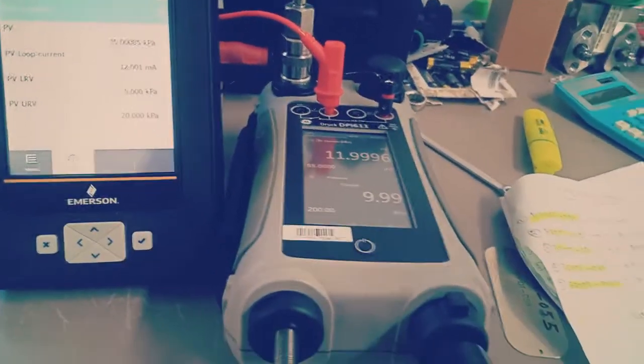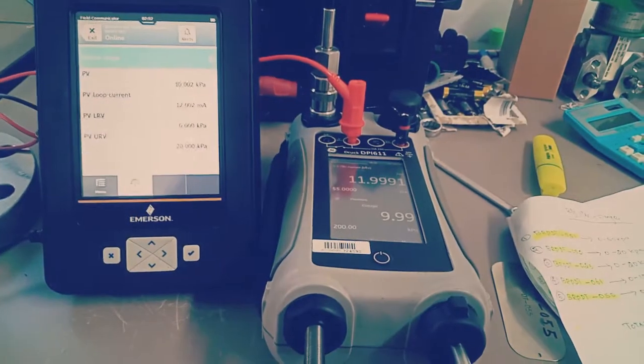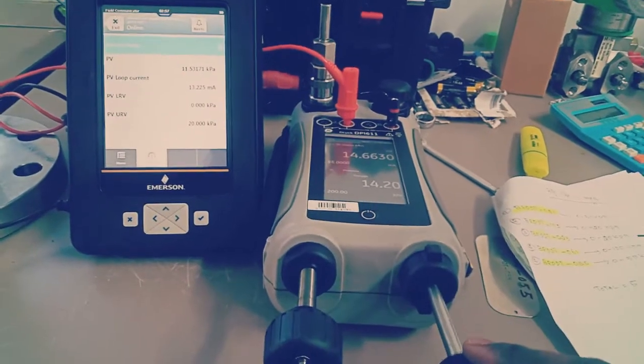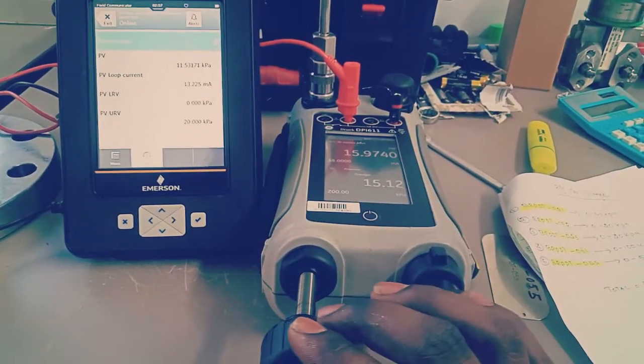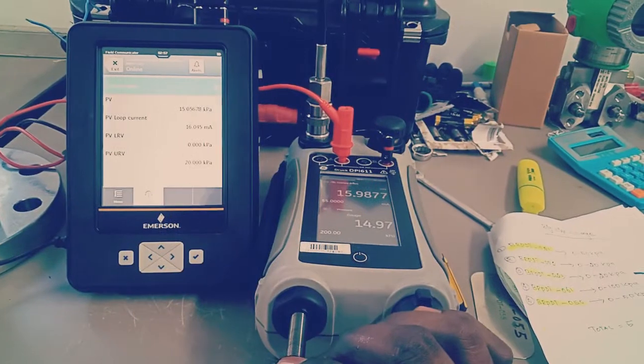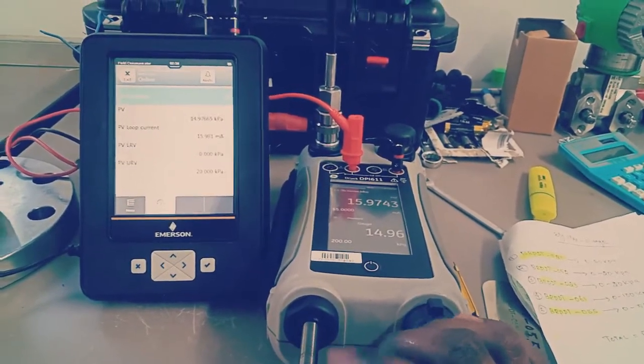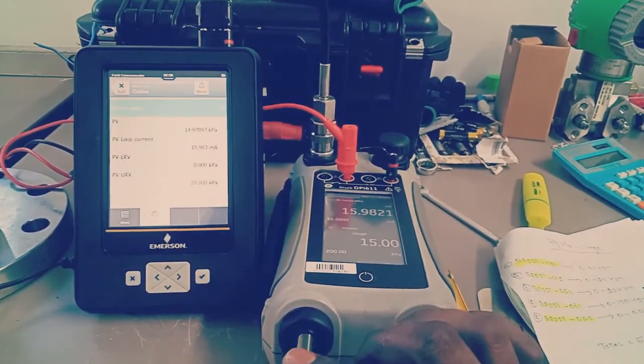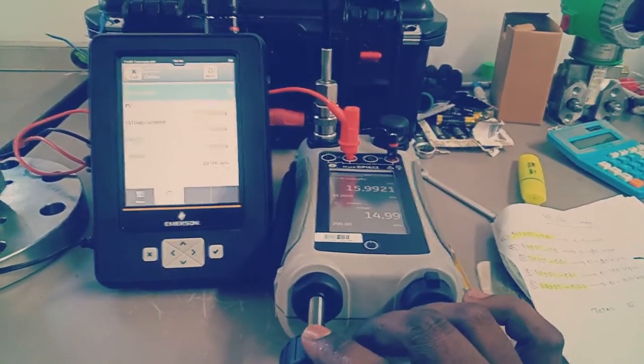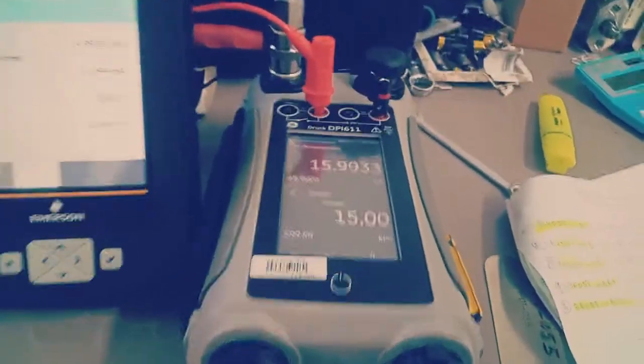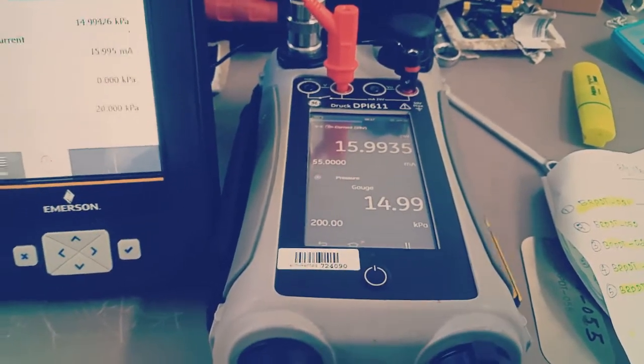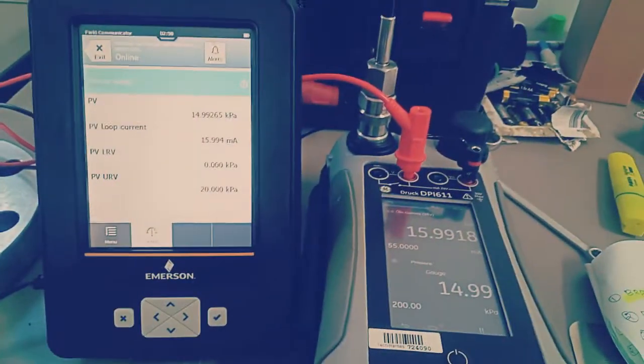Let's move on to 75 percent, from 10 to 15, 15 kilopascal. Just steadily increasing the pressure. It's almost there. This is 75 percent of transmitter capacity, and this is what we get: 15.993, so it is still below our tolerance limit, so it is acceptable according to error calculation.